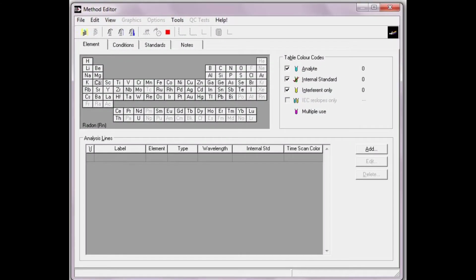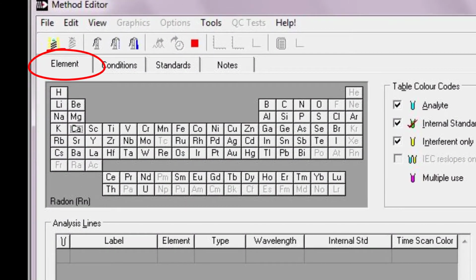In the Method Editor, you will see an Element tab with a picture of the periodic table. Here is where you will select which standards have been prepared. Remember that this ICP has an OES detector, so it's not possible to analyze every element, which includes the halogen family and carbon. Let's start this example by clicking on calcium.